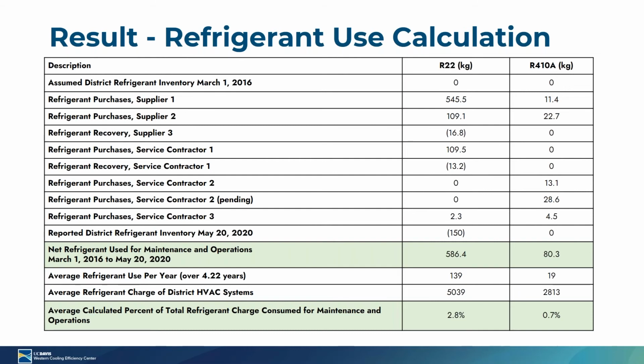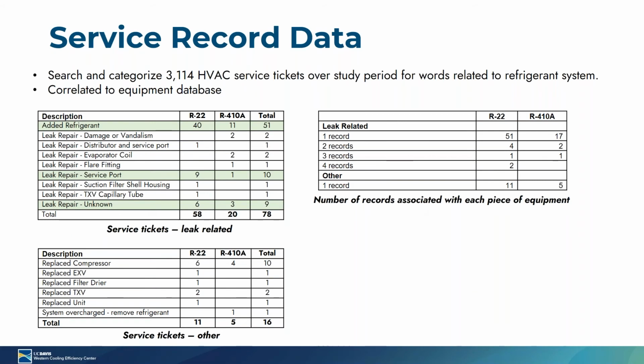We were also able to go through every single service record at the district. When a teacher reports that an HVAC system is not working, it creates a service record, and then an HVAC technician goes out and looks at the equipment, makes a repair, and documents their repair. So we were able to go through all the repair notes and provide some qualitative information as to what types of repairs are most associated with leaks. You can see here that we categorized every time a technician mentioned using refrigerant in some way, right?